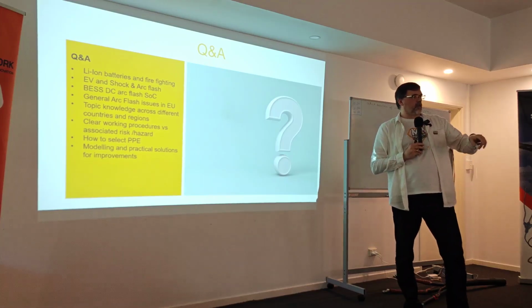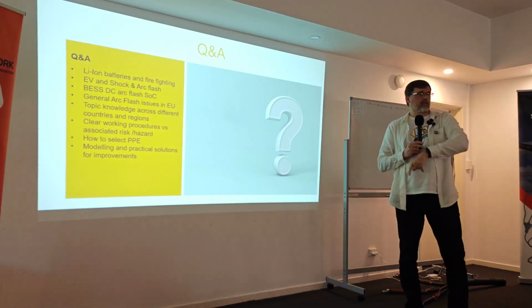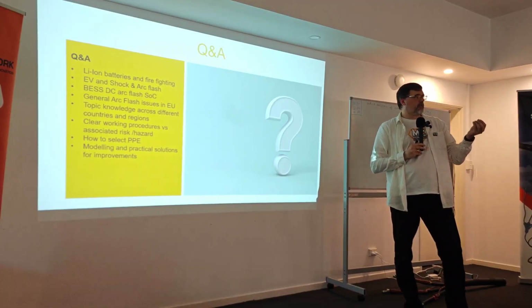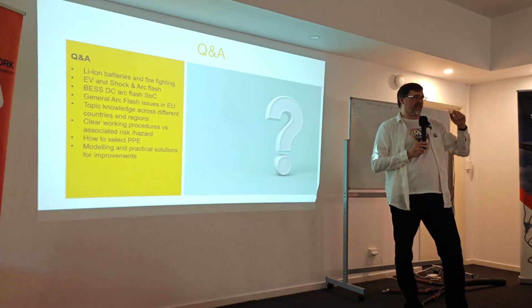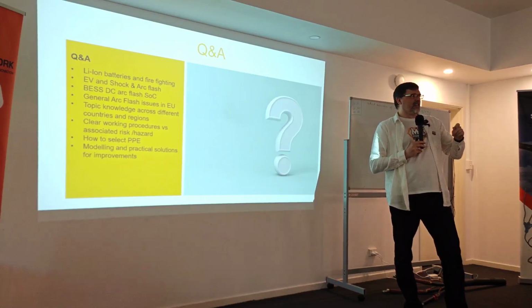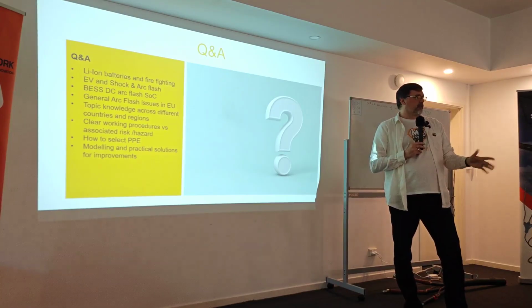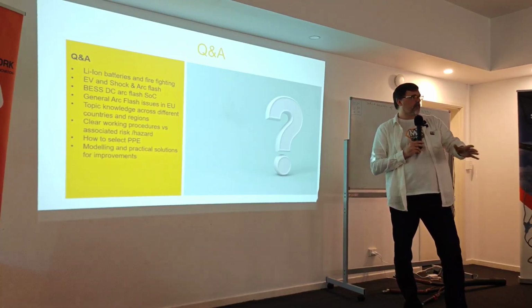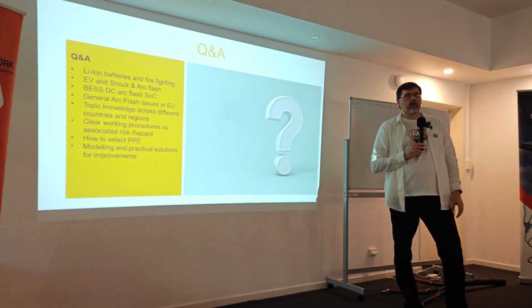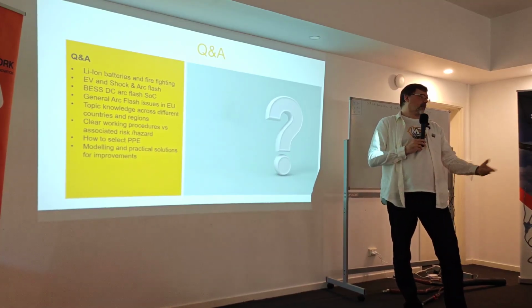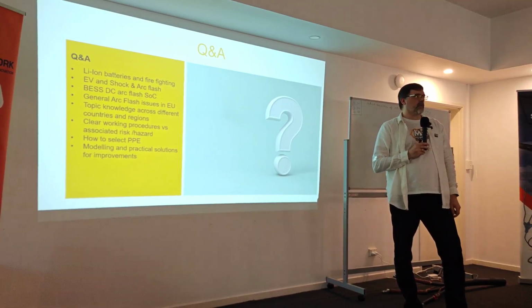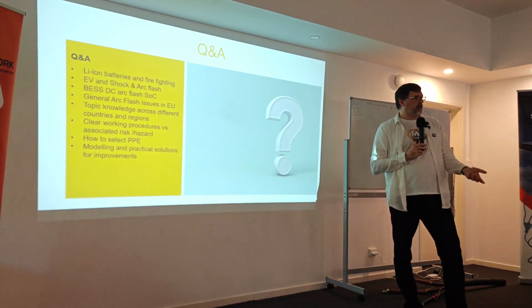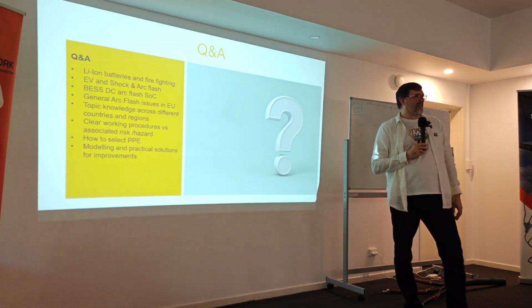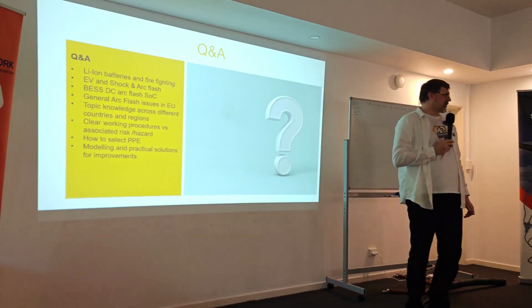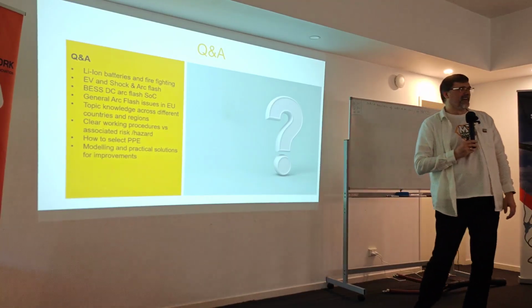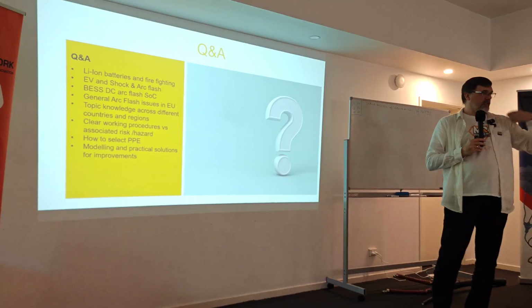When I was on the side, they had 9 stops on the production line, and they were all wearing electric shock gloves. I was like, huh? Because they assembled the battery. The whole battery was approximately 480 volts: if you assemble everything and charge it 100%, it will be 480 volts. And I was like, okay, so a shock hazard exists. I asked them how often they have to change, because they work 8 hours in rubber gloves, and I said they are probably not sweating. And they said, yeah, we do. Then I was walking with them and I was just randomly testing the gloves.